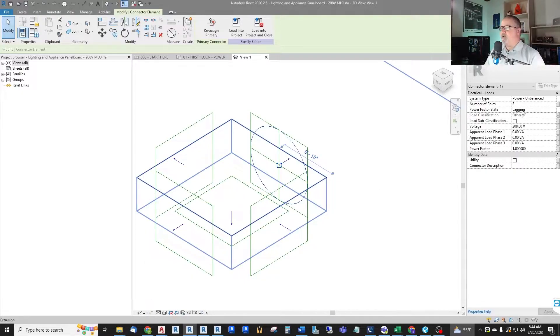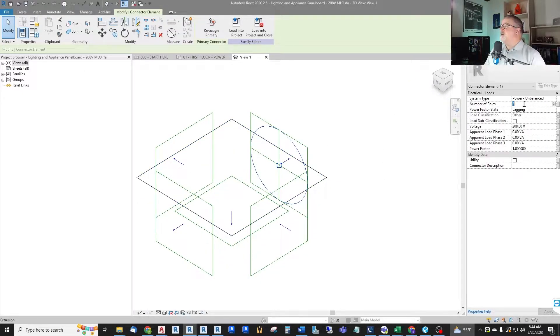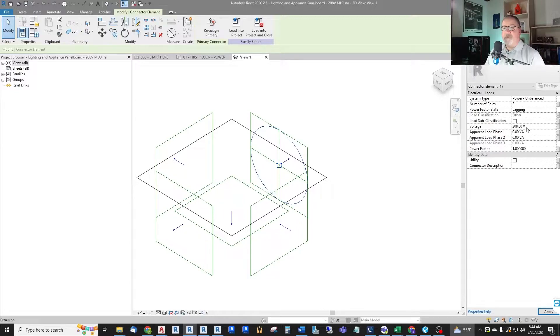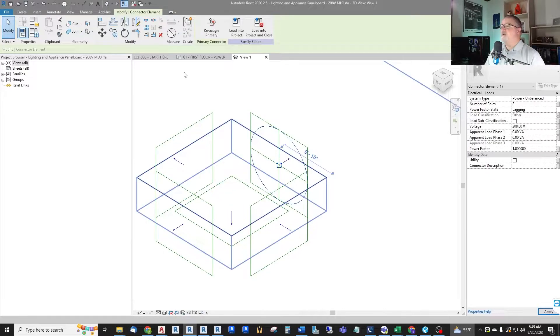So what I mean is I'm going to change parameters in this and save it as a different family. I'm just going to change this to two poles. 208 is what I want because I'm connecting this to a 120/208 three-phase four-wire Y system. So it's a 208 single phase and that's all I need to do and I need to save this as a family. I'll just save it here and I'm going to call it 208 single phase.